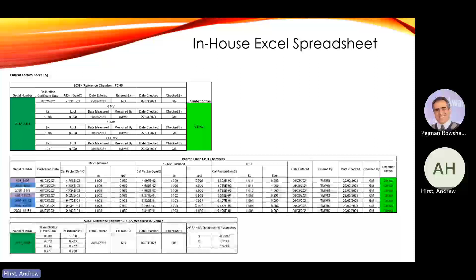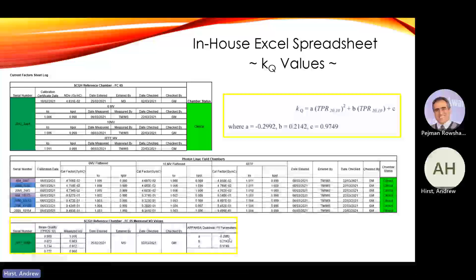So this is more on the practical or the clinical side of how we do it. This is our log of our spreadsheet. So as I said, after we take our TPR 20,10 measurement, we can plug it into here to get KQ values. So these were directly from the certificate: TPR 20,10s, the KQs, the fit parameters. And so once we've measured ours, we can get our own KQs. So that's KQ covered. Calibration coefficient from primary to secondary, just here. So that's directly from the certificate. You can see 48.31, and this one's in gray per nanocoulomb.